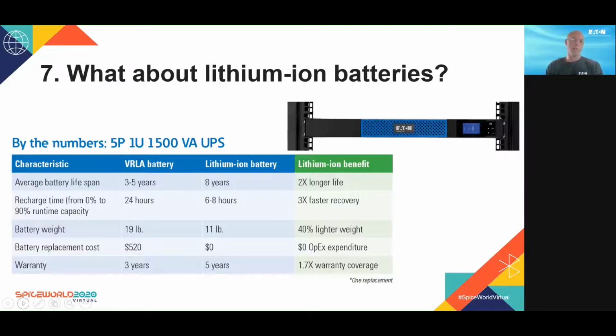The recharge time from 0% to 90% runtime capacity, 24 hours for the lead-acid battery versus 6 to 8 hours for lithium-ion. That's 3 times faster recovery. The battery weight, as mentioned, 19 pounds for lead-acid and 11 pounds for lithium-ion, 40% lighter weight. And then you have the battery replacement cost, $520 for an average lead-acid battery versus 0 for the lithium-ion battery. And why is it 0? Well, obviously because you're not buying a replacement battery at 3 to 5 years for the lithium-ion. And the warranty with this unit, you get 5 years for this lithium-ion unit, and you have 3 years for the lead-acid.